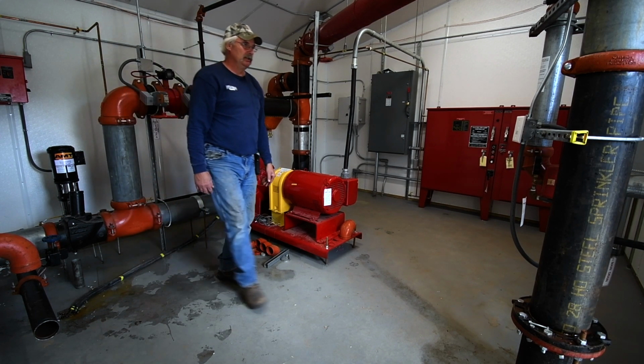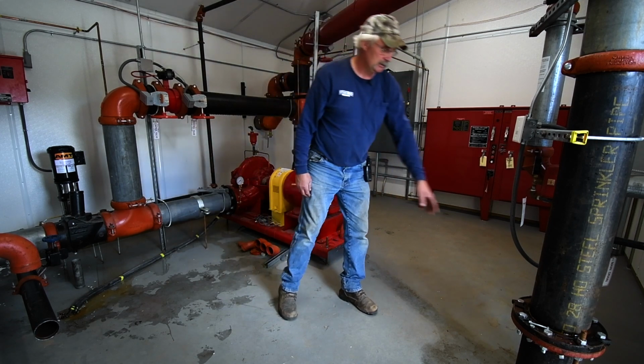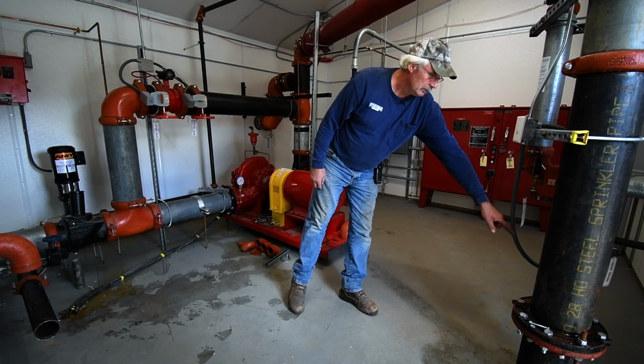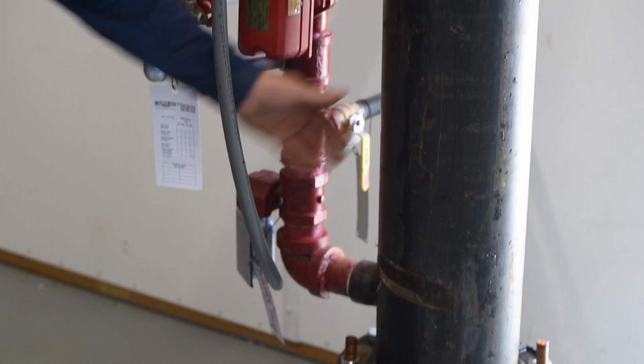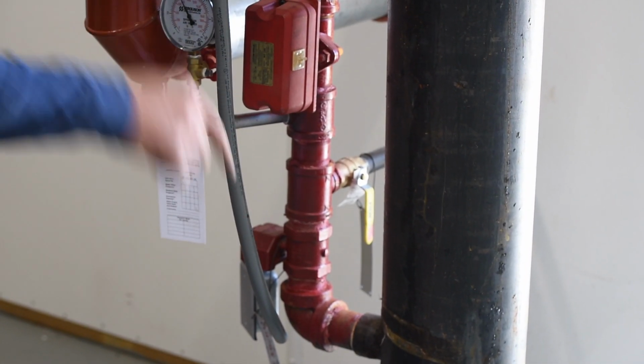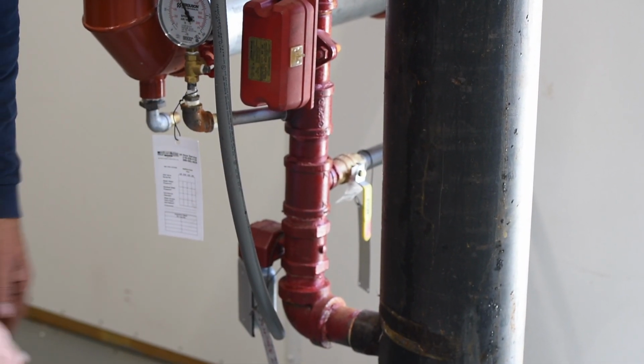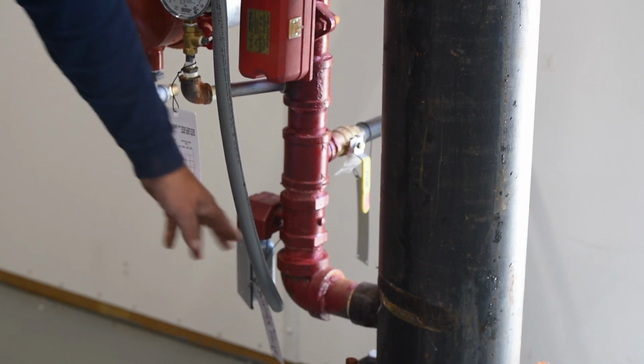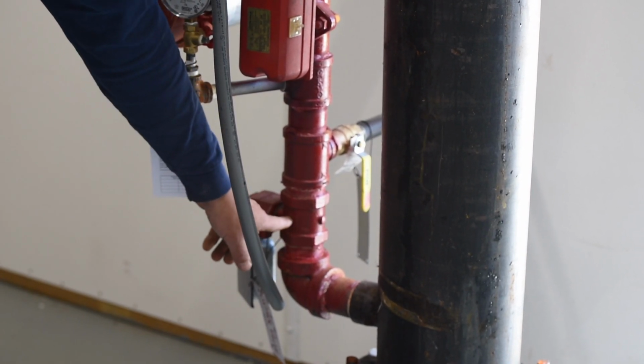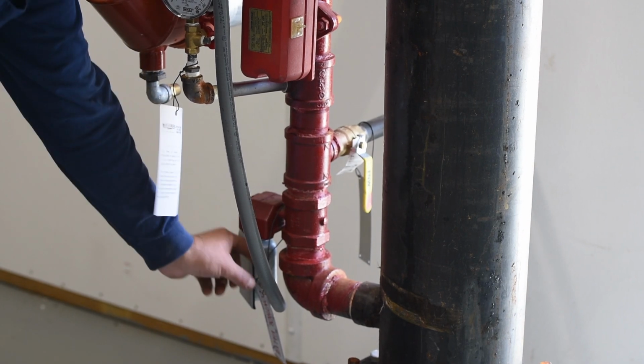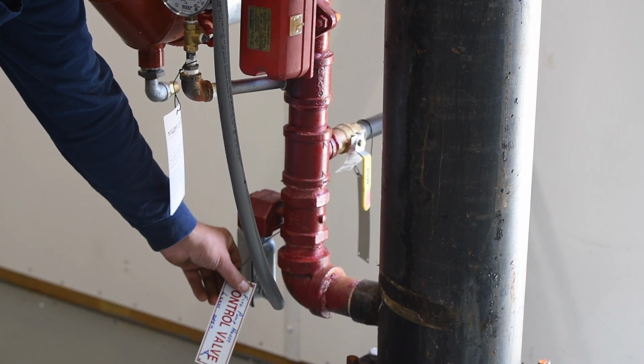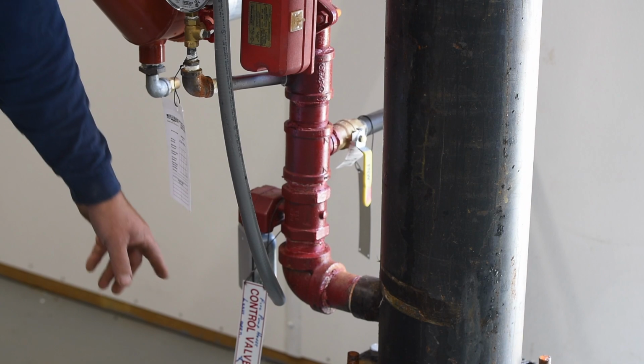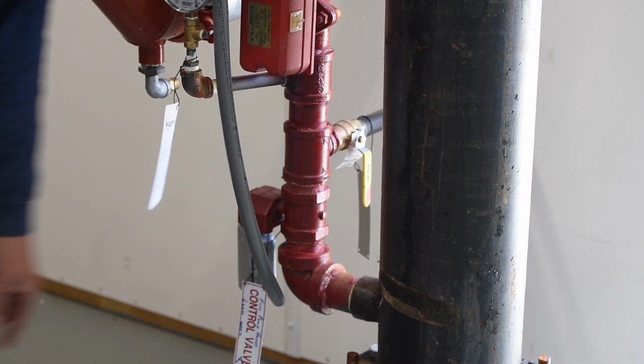The pump house itself has its own sprinkler system, which comes off the riser right here. Right here is the underground after the fire pump that goes down to the facility, to all the underground, to all the buildings. The pump house itself has its own system. Right off the get-go here is fire pump house, lead valve open, control valve A. So this valve will be always open.